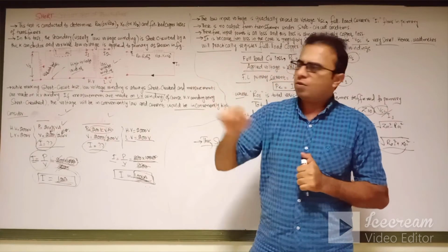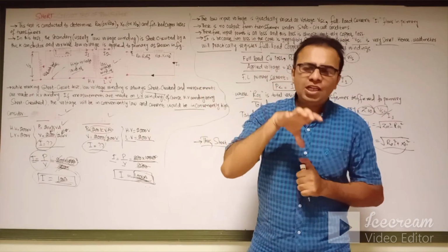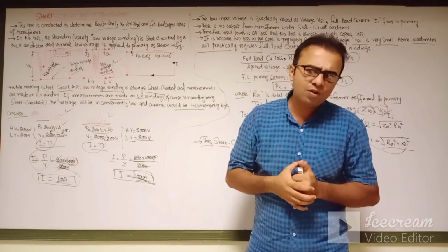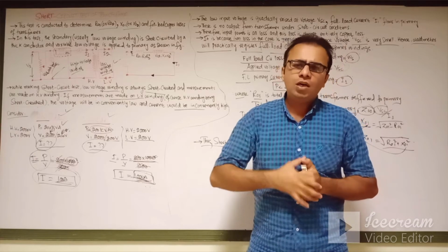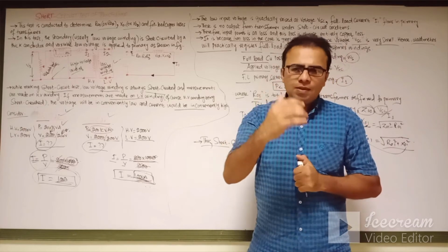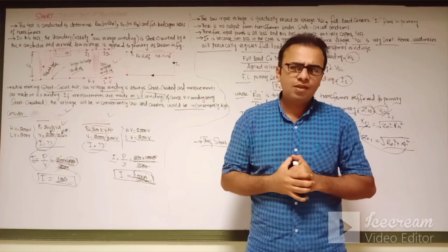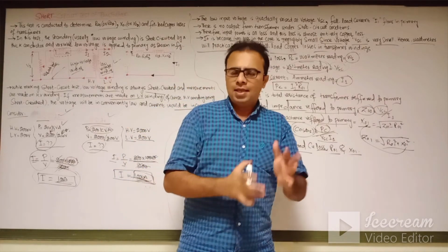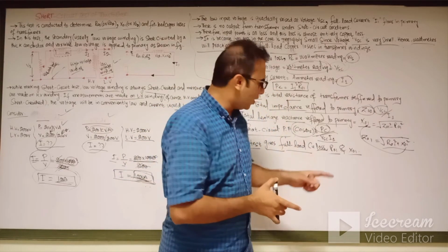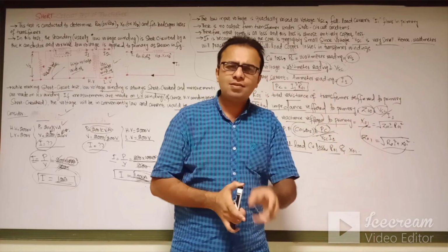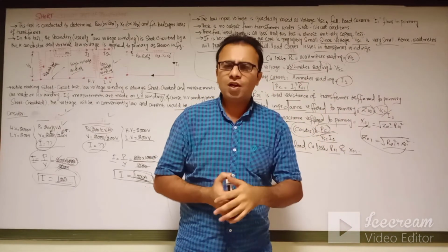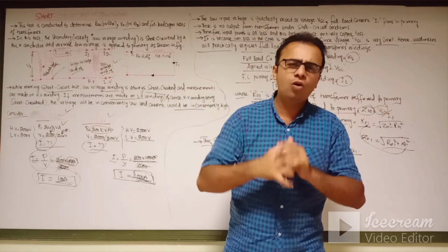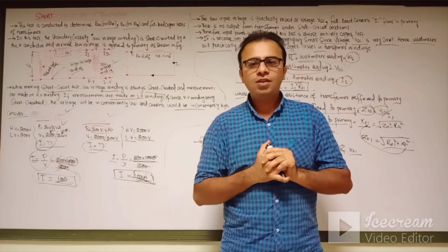When the applied voltage to the HV winding of the transformer is gradually increased up to VSC, the I1 current starts flowing in the transformer, and that gives the copper losses. This test is used to measure the copper losses in the transformer. Thus this test gives us the XO1 reactance and the resistance, and also the copper losses, and you can also find out the impedance from these parameters, because impedance combines the resistance and reactance components of the transformer.